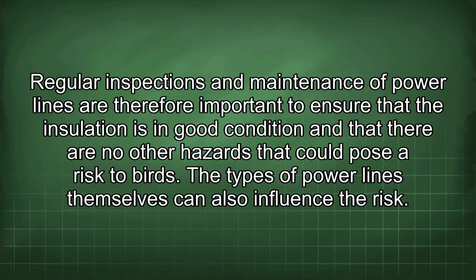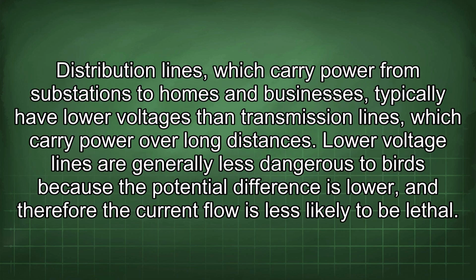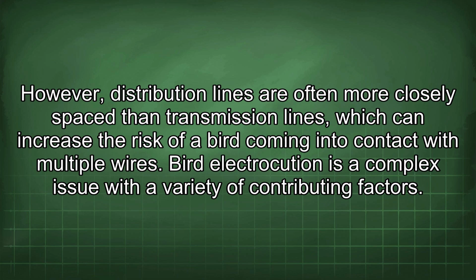The types of power lines themselves can also influence the risk. Distribution lines, which carry power from substations to homes and businesses, typically have lower voltages than transmission lines, which carry power over long distances. Lower voltage lines are generally less dangerous to birds because the potential difference is lower, and therefore the current flow is less likely to be lethal. However, distribution lines are often more closely spaced than transmission lines, which can increase the risk of a bird coming into contact with multiple wires.